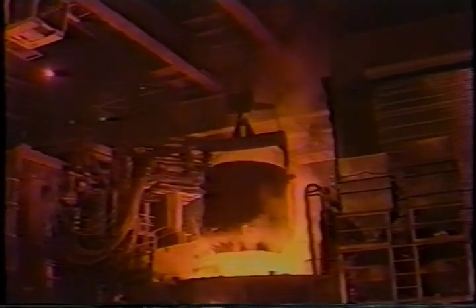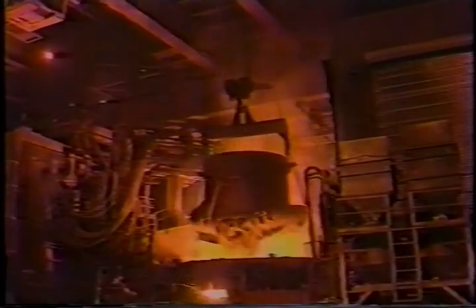Local conditions such as high humidity, salt-laden atmosphere, corrosive gases, heavy dust, or severe circuit operating conditions are considered to be abnormal and will require more frequent inspections. It should be emphasized that a series of brief inspections should be made at quarterly intervals until the progressive effects of the local conditions can be analyzed to determine a schedule which will maintain the equipment in satisfactory condition. The following general requirements should be helpful in setting up the program.